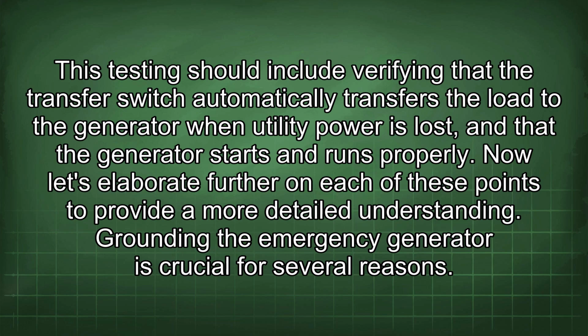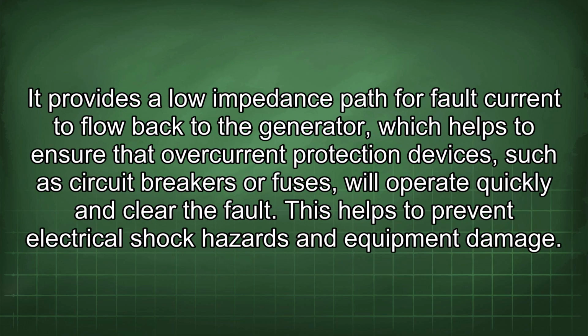Now let's elaborate further on each of these points to provide a more detailed understanding. Grounding the emergency generator is crucial for several reasons. It provides a low impedance path for fault current to flow back to the generator, which helps to ensure that overcurrent protection devices, such as circuit breakers or fuses, will operate quickly and clear the fault. This helps to prevent electrical shock hazards and equipment damage.